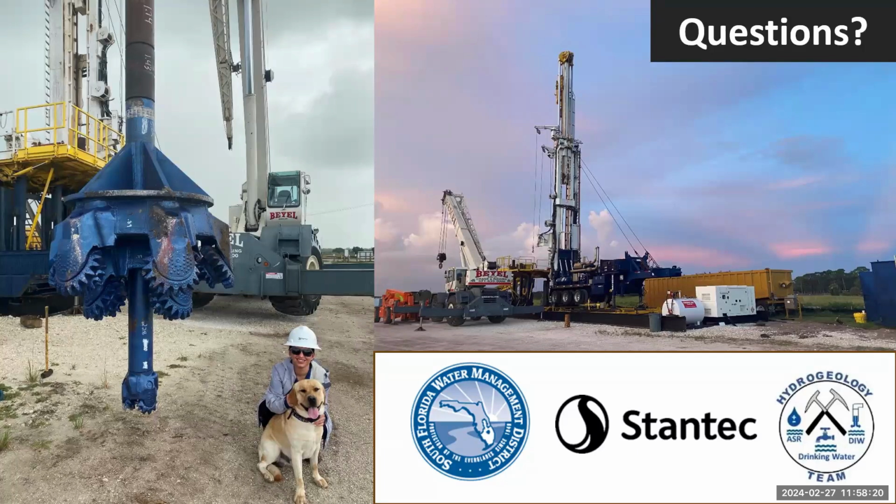So for the upper Floridan, since these wells aren't running constantly, we're going to be injecting water into them maybe 4 or 5 months, then storing it for 3 or 4 months, and then pulling it back out. I'm hoping that these wells will be 3 to 4 years, maybe even longer, between rehabilitation events, which is acidization for the upper Floridan, and then maybe 6, 7, 8 years for the APPZ. In fact, we have an APPZ ASR well over at L63 North that was installed in 1989 and has never been rehabbed. We pumped it at 10 million gallons a day, and we didn't pull the head off that well down to ground surface. So it's never been rehabbed, and it's still producing tons of water.